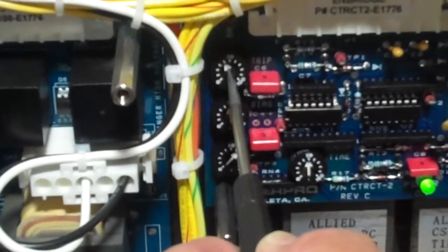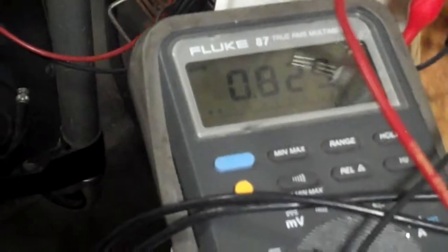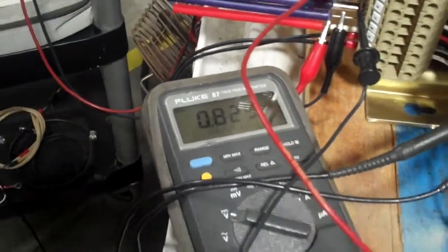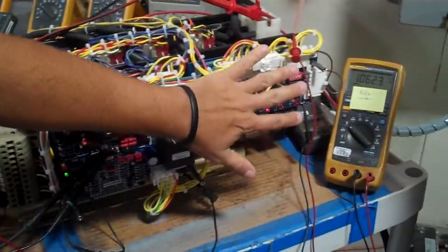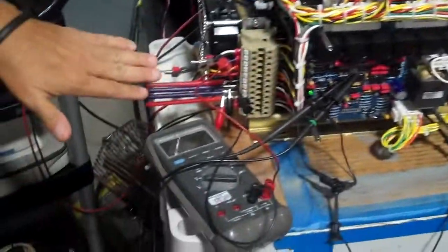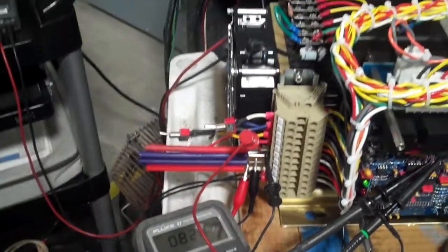So bring it back, Tony, to the point where you clear it. There you go. And that's it. You clear. Back again. Now the full sinusoidal wave at 10. And here we have again our 0.8 of a volt, not enough to energize the relay. This is the end of this video that shows you now that when you do trip, when you have a trip condition, the relay that is monitoring that signal will get energized.